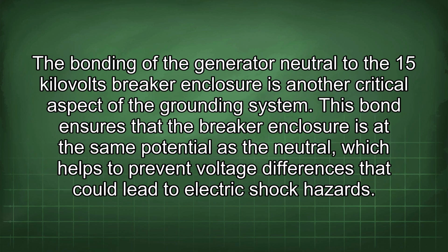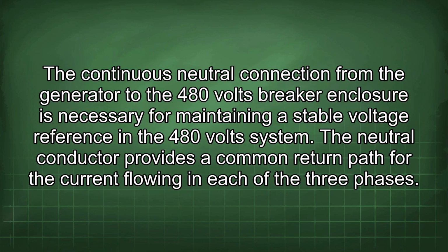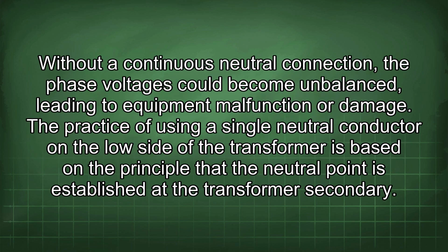The bonding of the generator neutral to the 15 kilovolts breaker enclosure is another critical aspect of the grounding system. This bond ensures that the breaker enclosure is at the same potential as the neutral, which helps to prevent voltage differences that could lead to electric shock hazards. The continuous neutral connection from the generator to the 480 volts breaker enclosure is necessary for maintaining a stable voltage reference in the 480 volt system. The neutral conductor provides a common return path for the current flowing in each of the 3 phases. Without a continuous neutral connection, the phase voltages could become unbalanced, leading to equipment malfunction or damage.